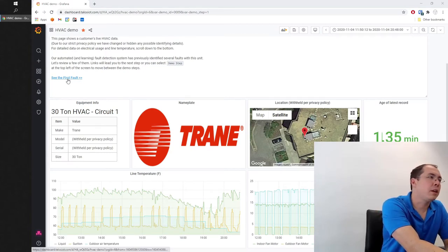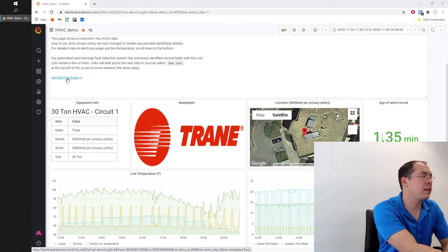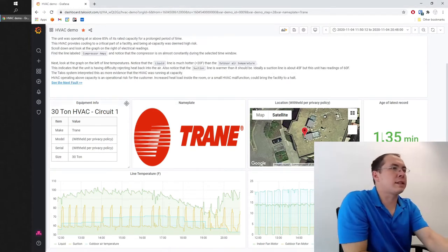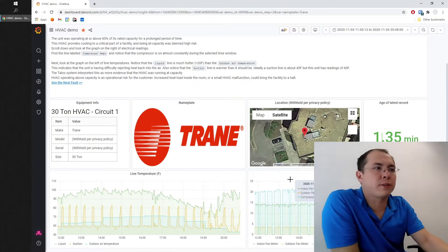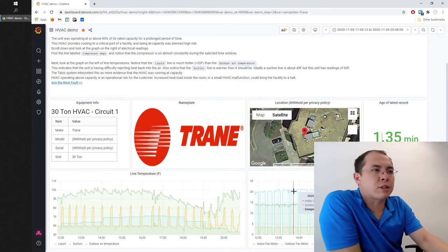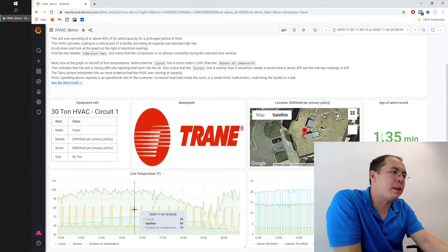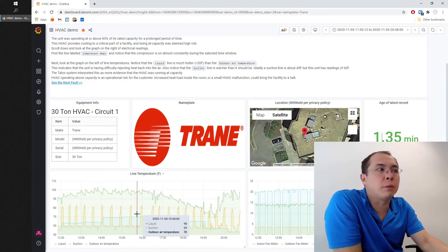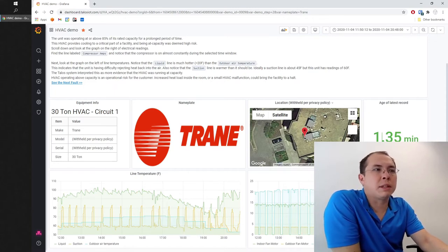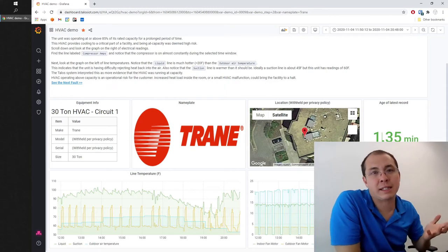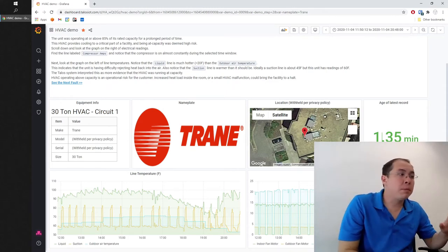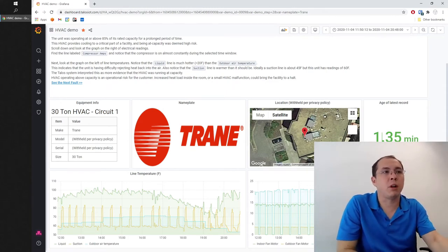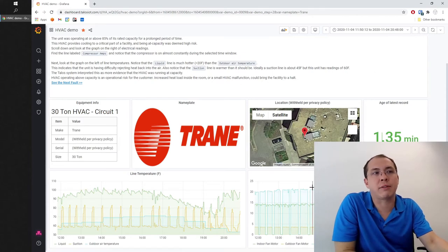So we can run some basic analytics on this. We can see some faults. Here's the first fault: this compressor is on a lot of the time, even though it's only 70 degrees Fahrenheit. That's bad, because if the next day were to be, say, 90 degrees Fahrenheit, which is uncomfortably warm, the people in this building are going to be hot, right? So this is a classic use case. The people in this building are still comfortable on this day that I've selected this data from.